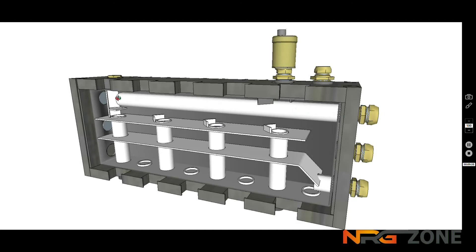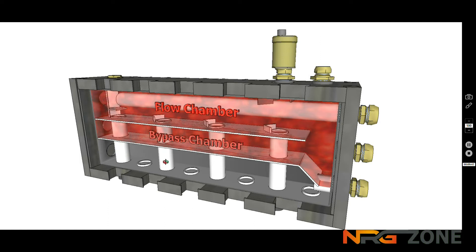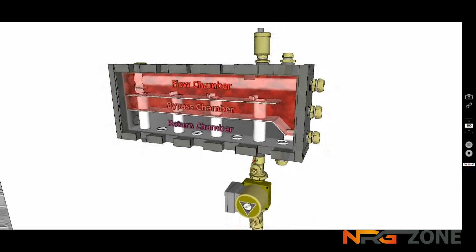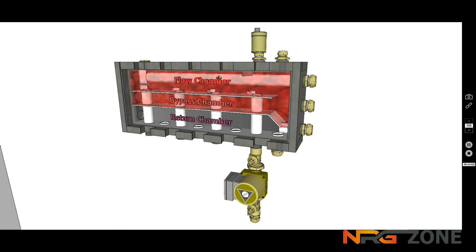The flow chamber, where water flows in from the right or from the left, will cause heat to be captured in that area and be made available to any of the zones, the outlet zone flow pipes. If that heat is drawn away by a zone, we introduce a pump. If the pump draws heat away to whatever it's going to heat, it'll be taking the hottest water. No matter what zone it's connected, the same temperature hot water is available at all times. When the water returns back in, it's collected in a lower chamber, and this water, as opposed to the standard low-loss header method, this water is separated from the other water. So if this is being offered back to a high-efficiency boiler, such as a condensing boiler or a heat pump, it's the coldest water that's offered back first. That would be supplemented only by any residual heat that leaves the boiler that is not used by the zones. Therefore, the energy zone manifold makes the system from the very start by far more efficient.